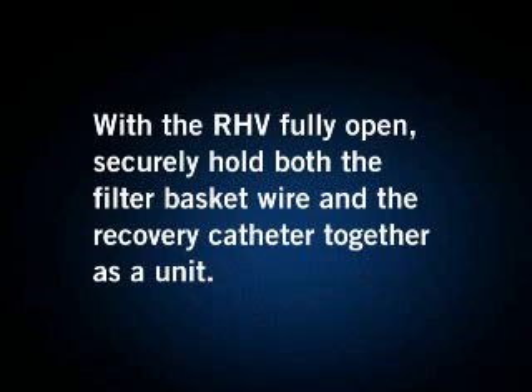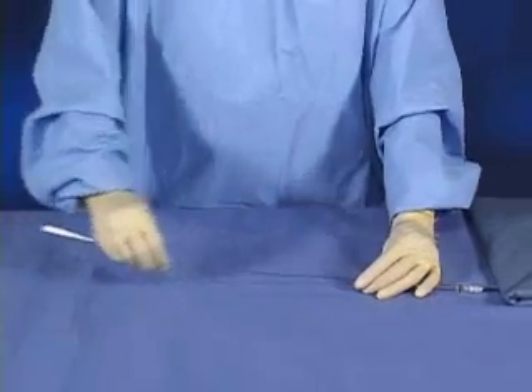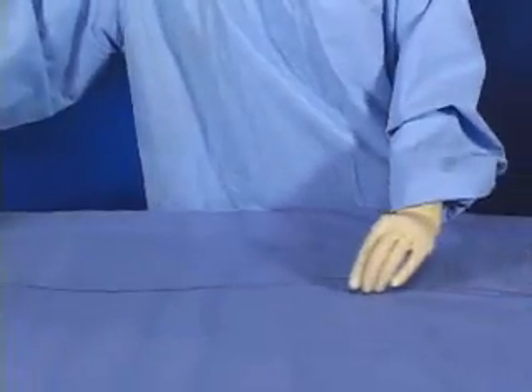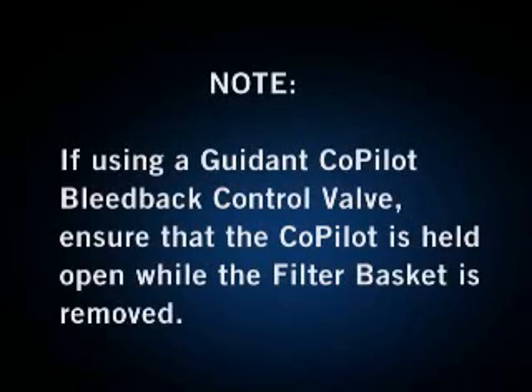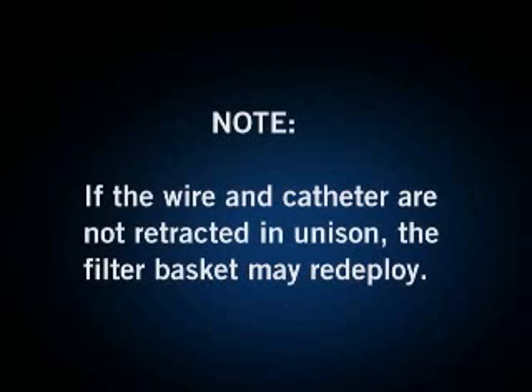With the RHV fully open, securely hold both the filter basket wire and the recovery catheter together as a unit, and slowly pull the system proximally into the guiding catheter or sheath and remove from the body. Note: if using a Guidant Copilot bleedback control valve, ensure that the Copilot is held open while the filter basket is removed. Note: if the wire and catheter are not retracted in unison, the filter basket may redeploy.